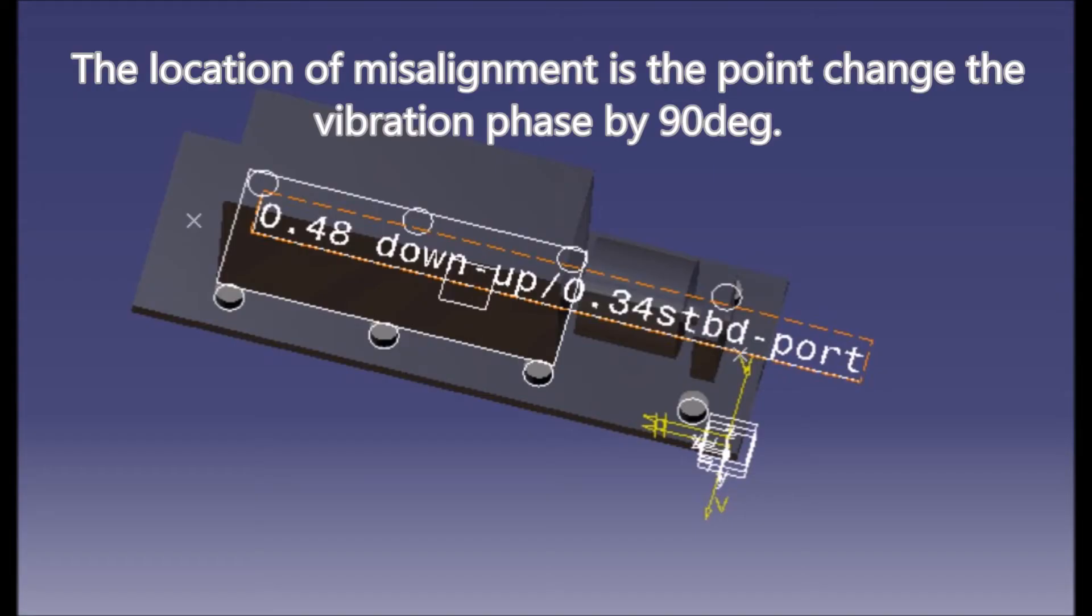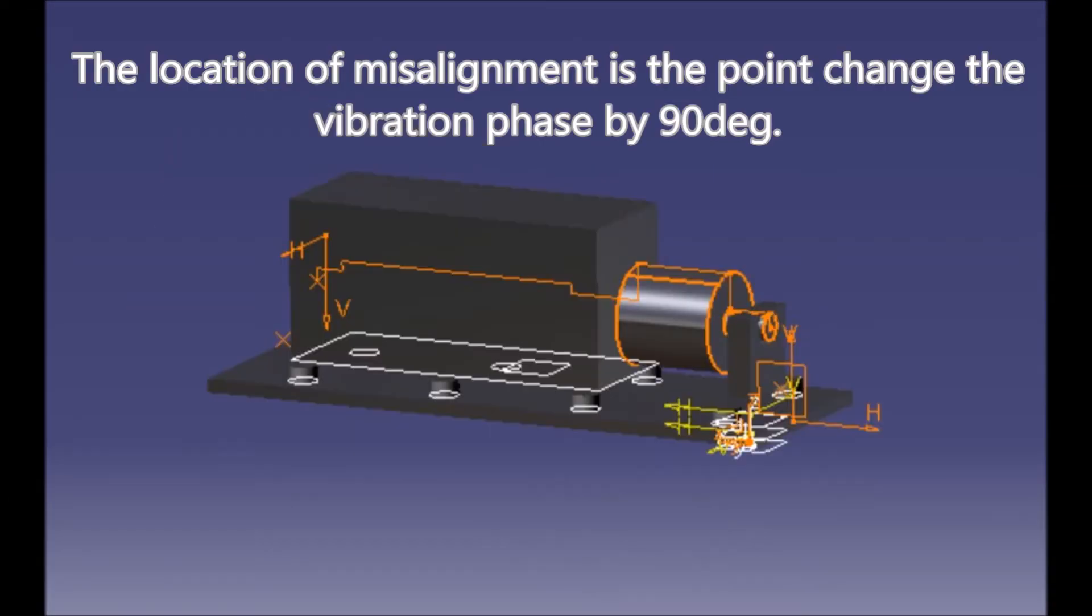The location of misalignment is the point where the vibration phase changes by 90 degrees.